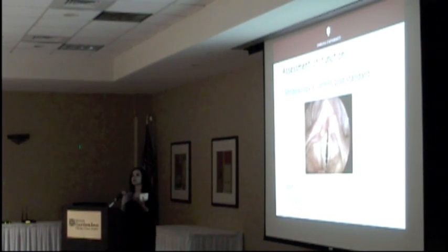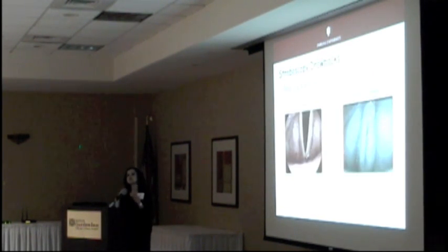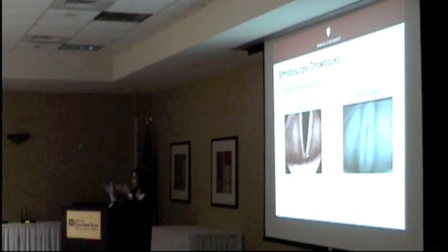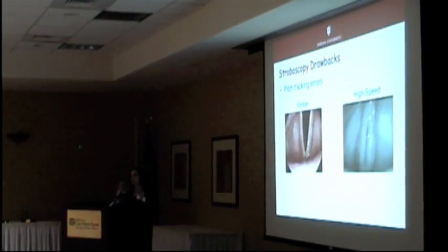So vocal folds vibrate in females around 200 times a second, and in males around 120, 100 times a second. So this is very, very fast, and our eye cannot see it. So we slow it down with this technique called stroboscopy, where you see an average motion. But when voice is severely affected, the laryngeal microphone really cannot capture the pitch of the voice. And so it in turn does not trigger the strobe light to latch onto something which is steady. And so what you see is an artifact.